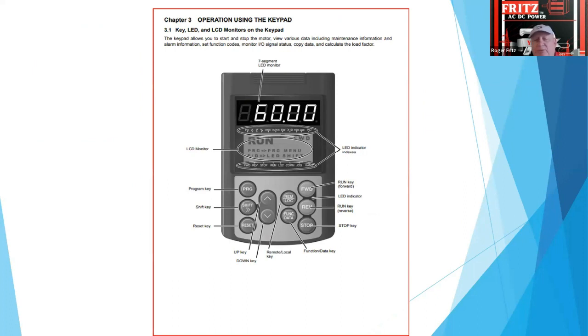This is a little bit more about the digital operators that are on the front. I also give classes on specific drive control applications. We've done it for extrusion machines, because you have encoder feedbacks, and most drives you can use in multiple modes, whether it be sensorless vector, full vector, where you have the encoder feedback, or you can have it in volts per hertz, or you can have regulated volts per hertz, which is more the latter ones for fans and pumps. So it adjusts the curves and then automatically regulates.